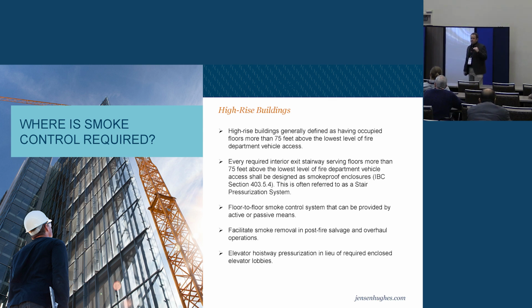If you have specific questions, feel free to reach out to me afterwards and we can talk about your example. Some of the obvious ones: every interior exit stairway that goes from 75 feet down has to be a smoke-proof enclosure, and it has to be protected by mechanical means likely. So likely you have what's called stairwell pressurization. Very commonly I see it not working. If you ever see smoke detectors outside of your stairwells, those are mandated. The job of those smoke detectors is to activate the fire alarm, but also that stairwell pressurization system. Floor-to-floor smoke control, we'll talk about those later. All of these we're going to go into a lot more detail on. With a smaller group like this, I never mind answering questions. I did only practice this from the beginning, so I have to start over, but I certainly don't mind questions. No, I'm kidding. Fire away. This is a nice group to have conversational discussions.